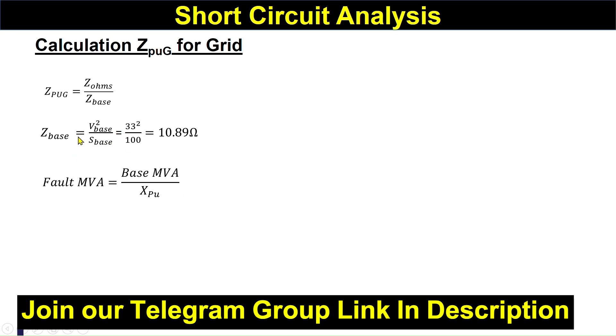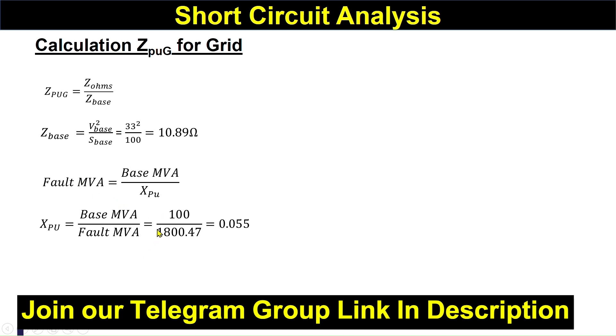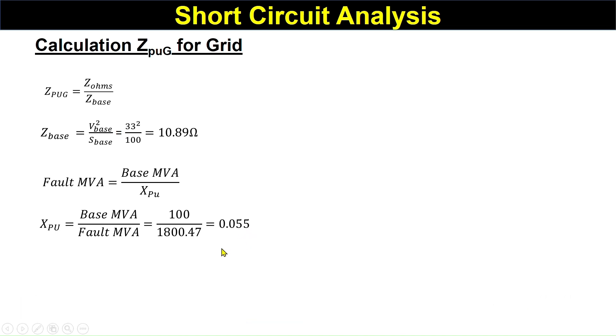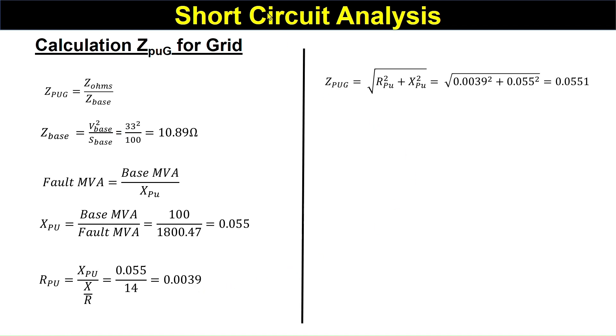The fault MVA equals the base MVA divided by X per unit, so X per unit equals base MVA divided by fault MVA. With base MVA of 100 and fault MVA of 1800.47, X per unit becomes 0.055 per unit. Then R per unit equals X per unit divided by the X/R ratio. With X per unit of 0.055 and grid X/R ratio of 14, R per unit becomes approximately 0.0039.